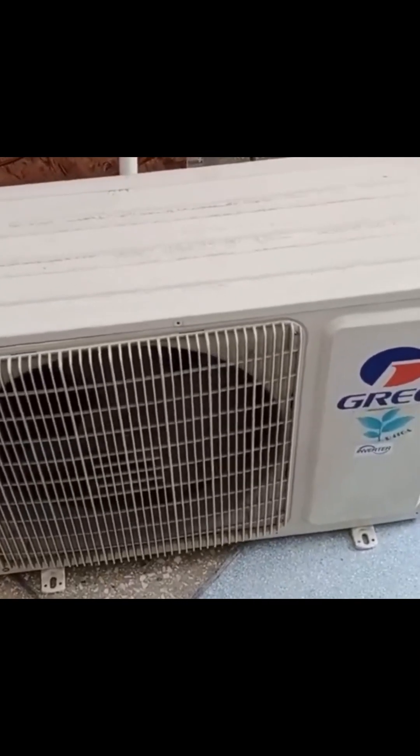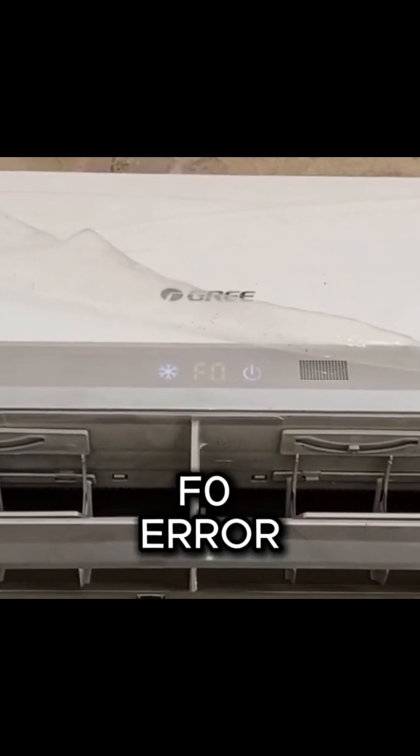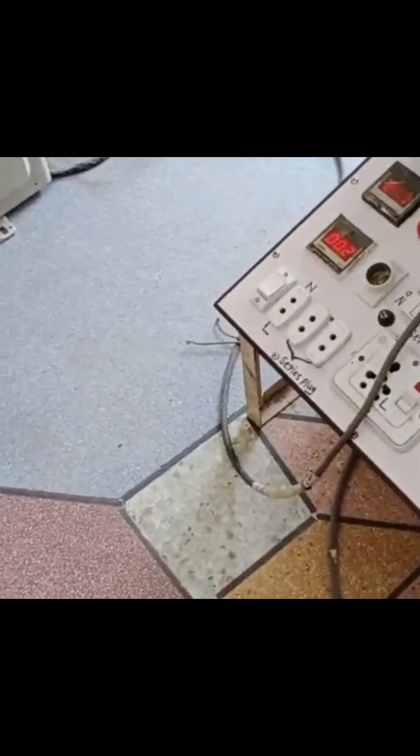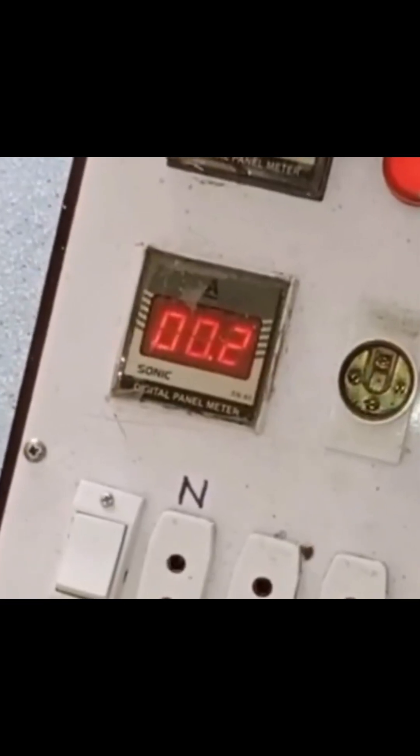The outdoor of a Gree mini split air conditioner has completely stopped and the indoor unit is displaying an F0 error code. I will explain why this error is occurring. You can see that I have turned on the switch but it is only showing 0.2 amps and the unit is not operating. The red light is on on the display of the unit.